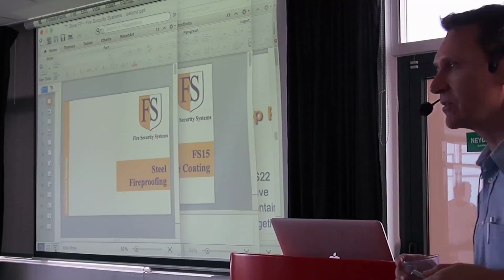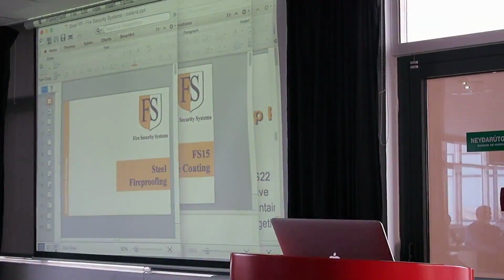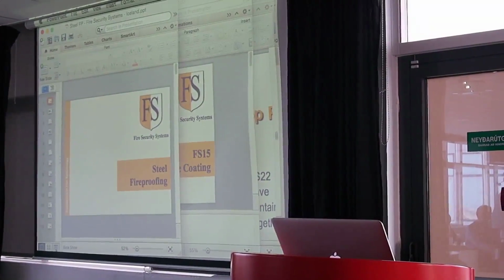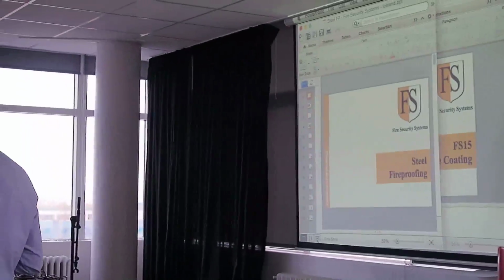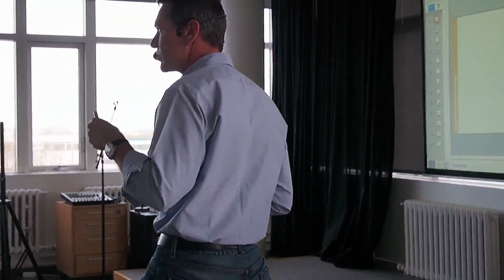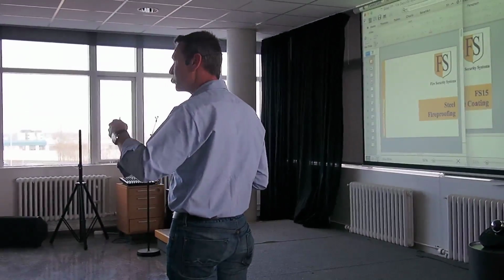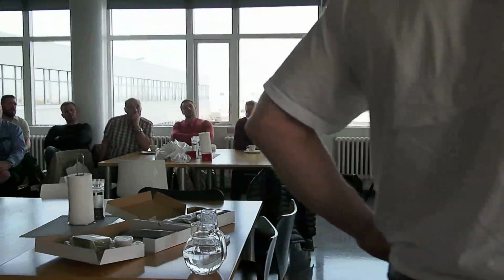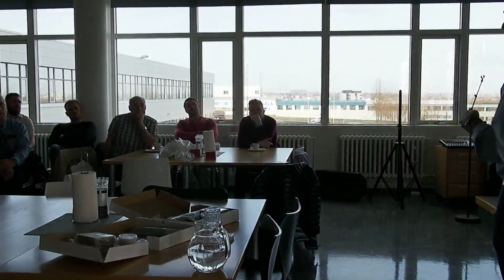About saving the cable, so you can run the cable after the fire. Yes, after the fire, what we would do is scrape away, not unlike the movie you watched, the cable coating, and replace the burnt cable coating, because it never gets down to its final thickness, and we'll be doing that while the cable's still active.